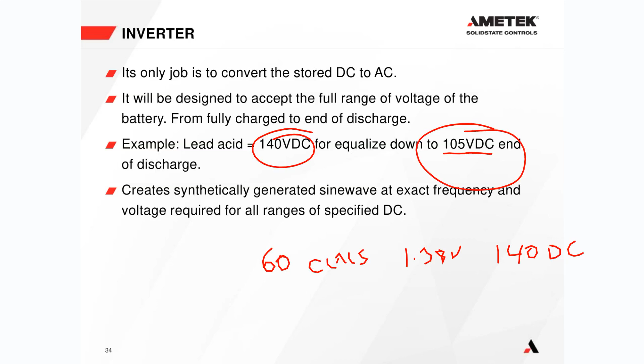And then also, if we do have a power failure, the battery is going to start to discharge. And then eventually it will get down to 105 volts DC, which is the industry recommended voltage for end of discharge. So the inverter will be designed to work between 105 volts to 140 volts without any issues whatsoever. And what the inverter does is it creates a synthetically generated sine wave at the exact frequency and the exact voltage required for all the specified ranges of DC.